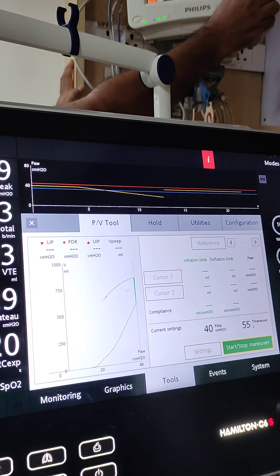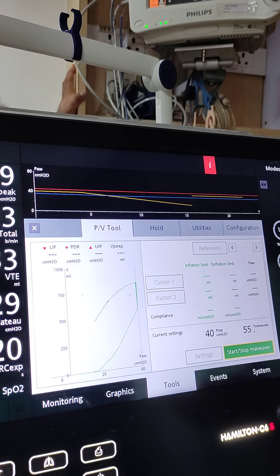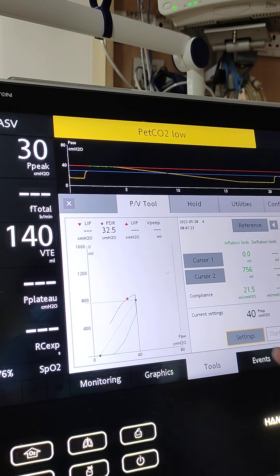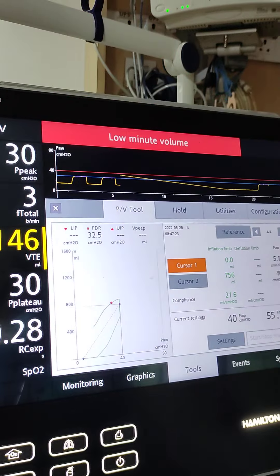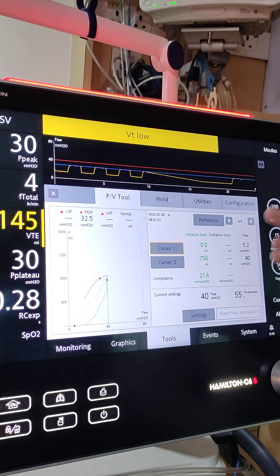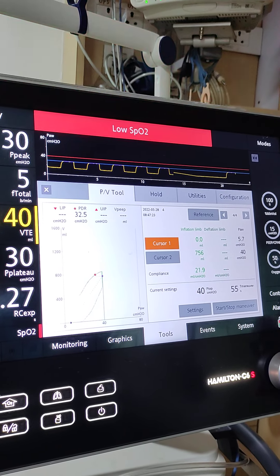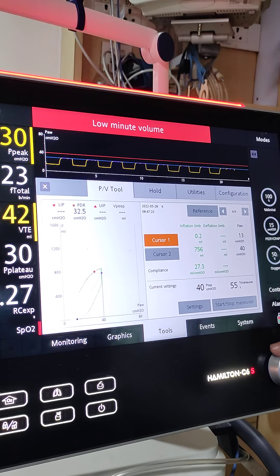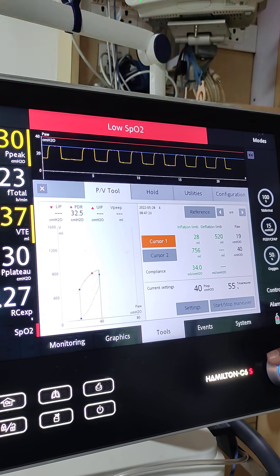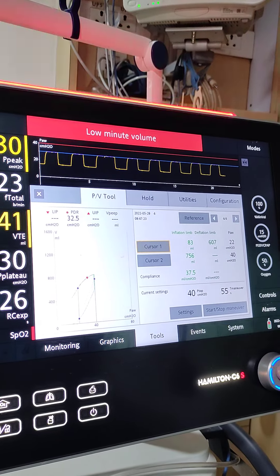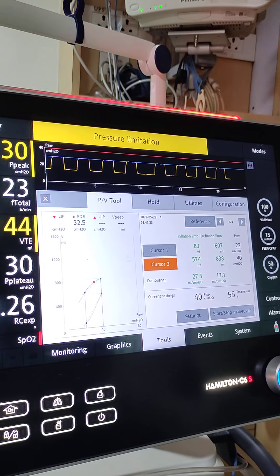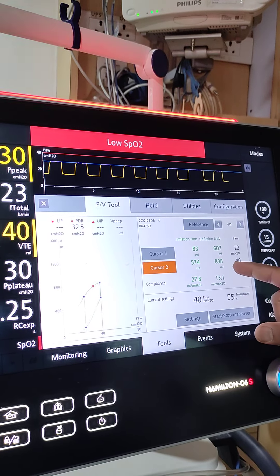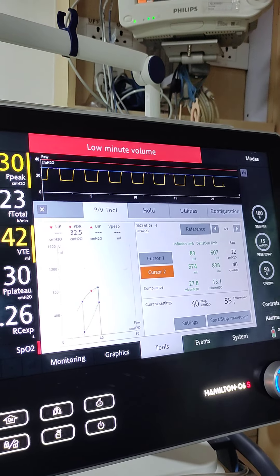We are just inflating the lung — we are not ventilating, we are only inflating the lung. So when we inflate the lung, in 5 minutes time we should see an improvement in oxygenation. It is going to go and stop at 15. So it has now found a volume over here. Let us see what volume is optimal — optimal PEEP not yet.